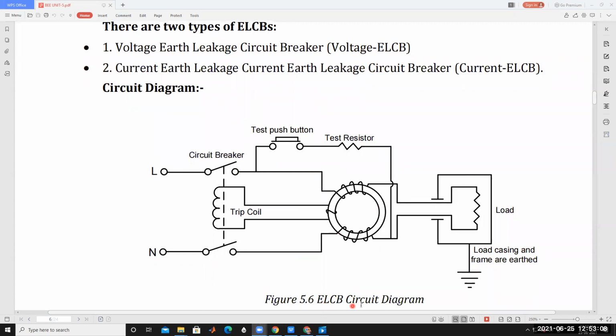This is the circuit diagram of the earth leakage circuit breaker. This is called the line supply, and this is the neutral supply. Here the test push button is used to check whether the ELCB is working properly or not. This is called the test resistor, and this is called the CBCT, the core balance current transformer.